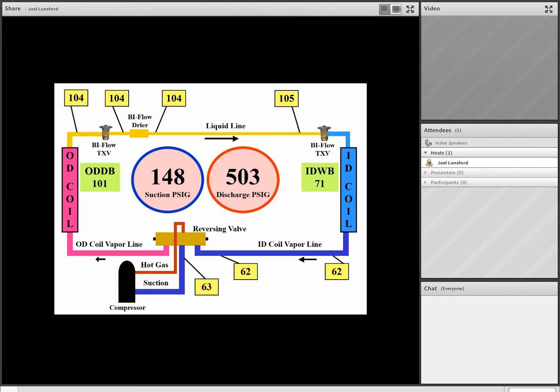This is a classic overcharge with an operating and functioning expansion valve. So suction pressure is about normal, superheat's about normal, but our discharge pressure is high and our subcooling is very high. So the indoor TXV is operating properly. It's throttling the refrigerant like it should. But remember, team, with a system that's equipped with a TXV, we always use subcooling as our method of charging.